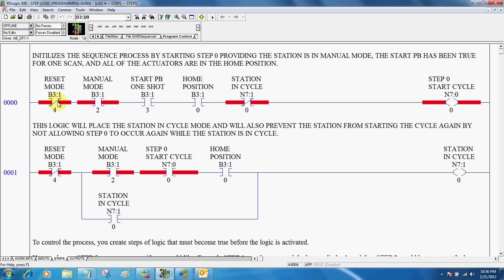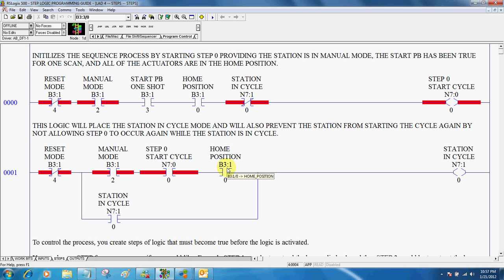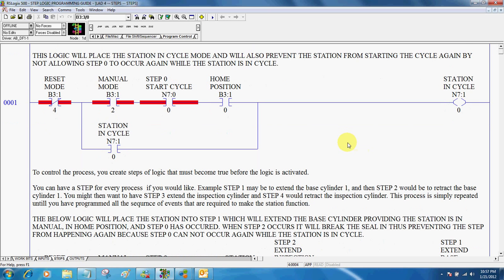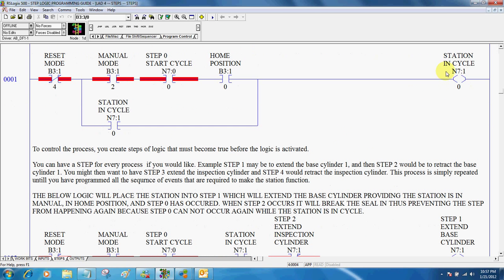So one of the first things is you want to start your cycle. So if you're in reset mode, you're in manual mode, the one shot becomes true, and you're in home position, you're going to get step zero to occur. So step zero occurs, comes down here, occurs down here. As long as you're still in home position, that will put your station in cycle. Now notice, when it's in cycle, this bit here becomes false, so step zero can't happen again. And that's a very important thing, because we don't want our sequence of operations to begin again until we tell it to.